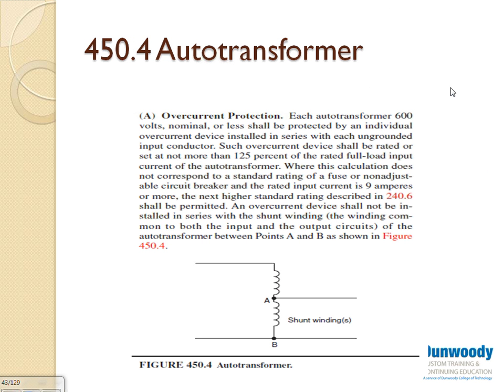Okay. If you have an autotransformer, there are a couple of things you have to keep in mind. For example, they don't want you to fuse this. God forbid you go fuse this area here. Imagine fusing that common area here. So each autotransformer shall be protected by an individual overcurrent protection device rated at 125 percent of the rated full load input amps. So, a couple of things about the autotransformer.